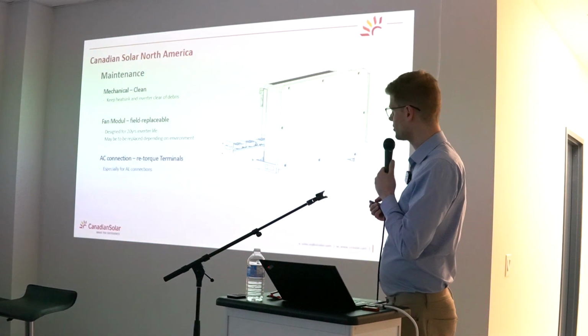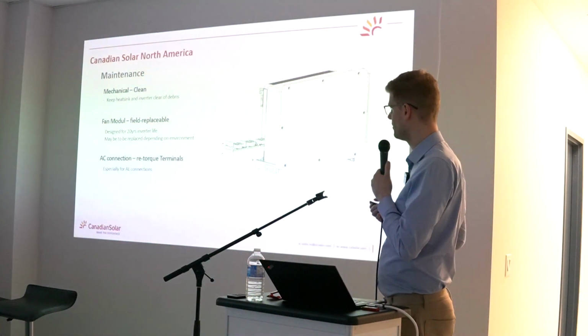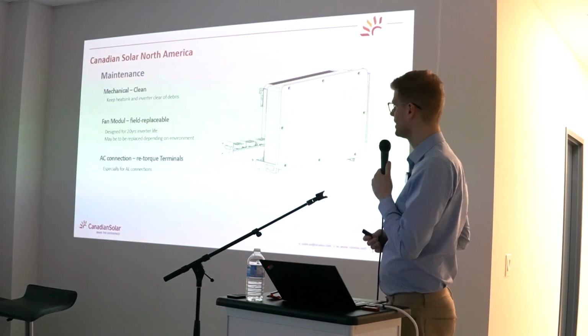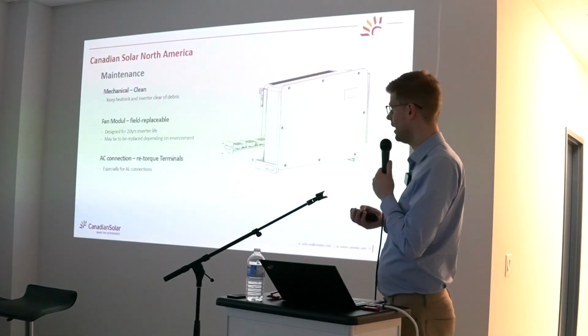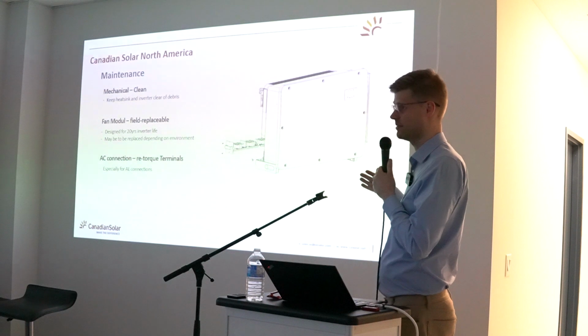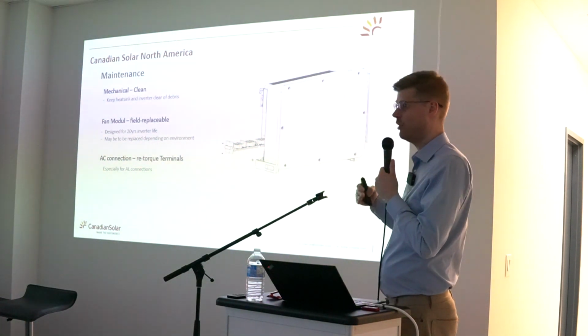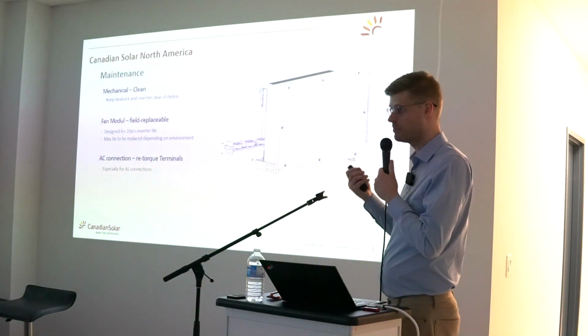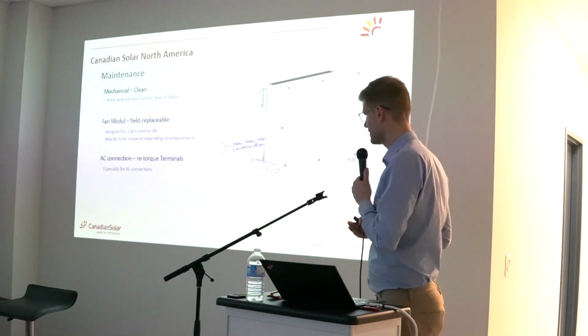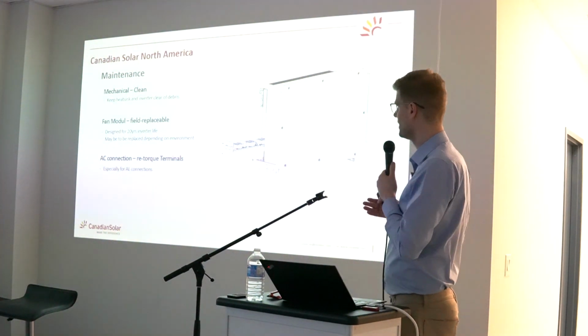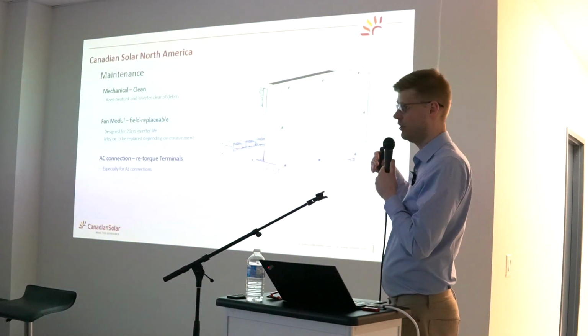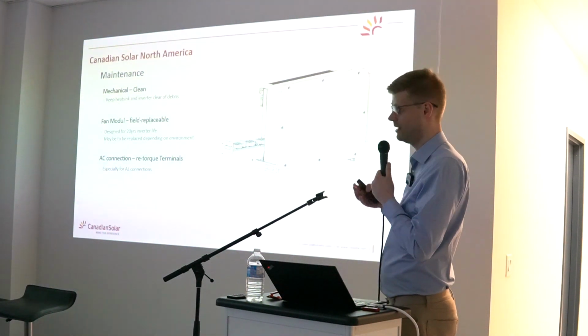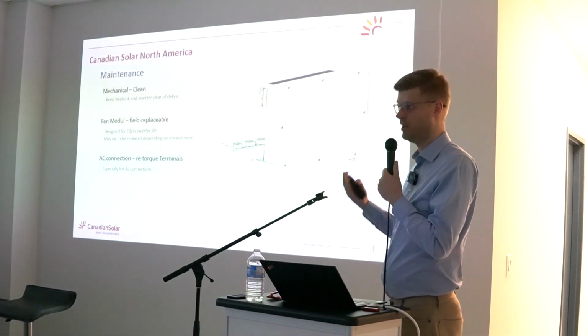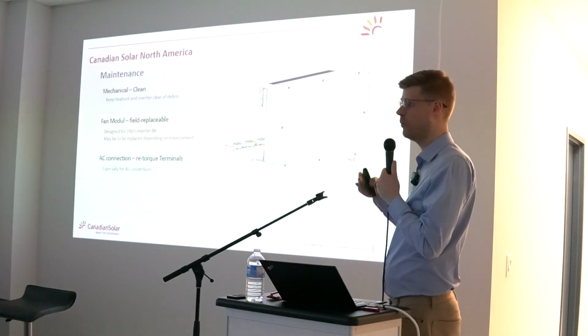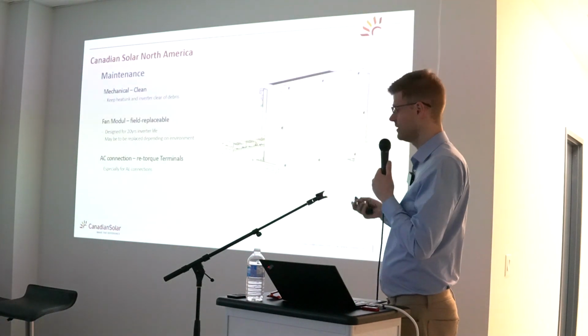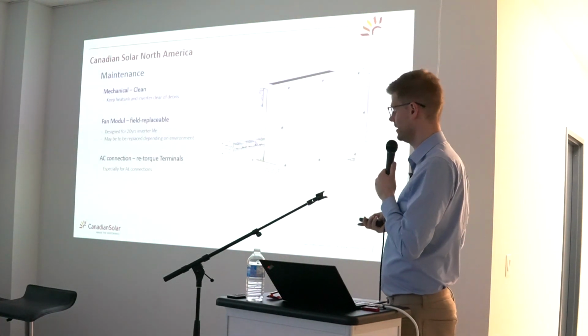The fan board is actually a slide-in module where all the fans are mounted on a tray. And you can take the fan tray out, for example, if you are installing the system in an agricultural environment where you have a lot of dust and a lot of large particles from whatever grain or whatever it is, or just a road that is very dirty, you can accumulate quite a bit of dust on those blades and on the fans, so you can take them out, you can clean them, or you can also replace them after 10, 15 years when there is a fault on the fans, and you have the possibility to do that very, very easily in the field.